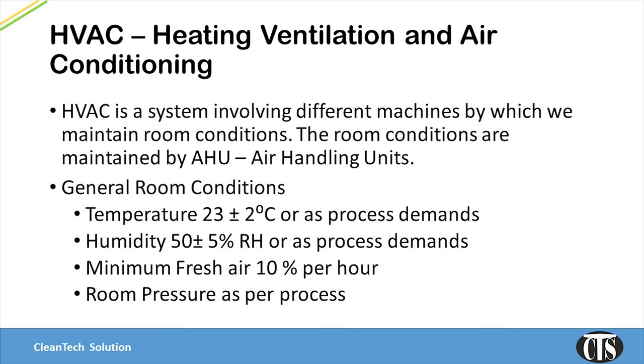Besides particle count and microbiological load, we also maintain temperature, lux, pressure, and humidity in our rooms. We generally maintain a temperature of 23 ±2°C and humidity of 50 ±5% as these are comfort levels for working. But there are some products where lower temperature and humidity are required.